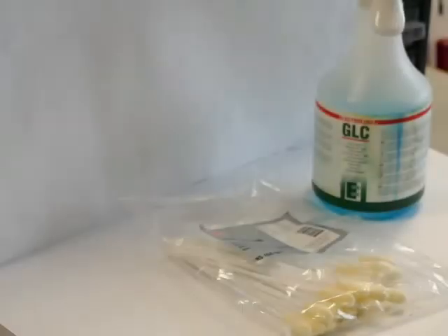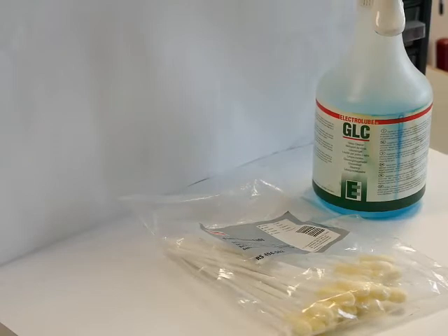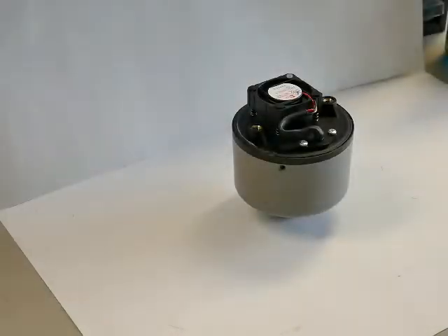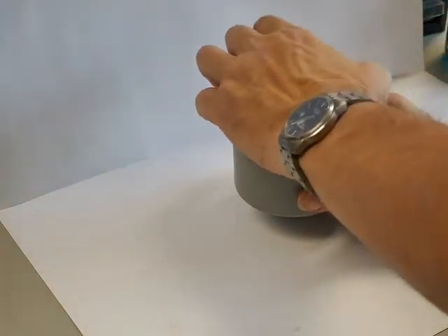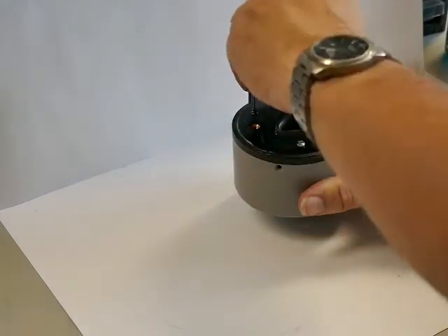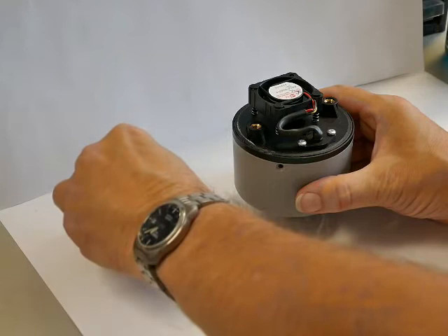To clean the detector, you will require the foam buds, and glass cleaner supplied in the detector service kit. A smaller bottle of glass cleaner is supplied in the service kit than the one shown here. To clean the detector sample chamber, you need to remove the fan. The easiest way is to place your hand over the fan. This prevents the fan retaining plug being lost. Then ease up the fan to release the retaining plug.